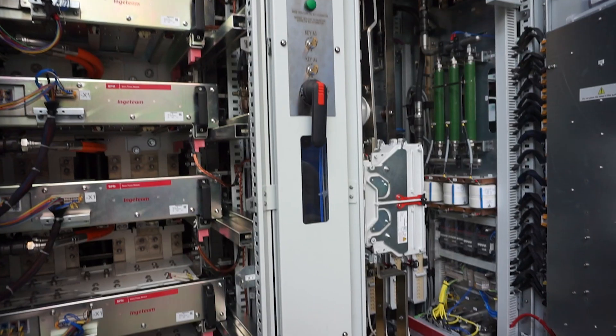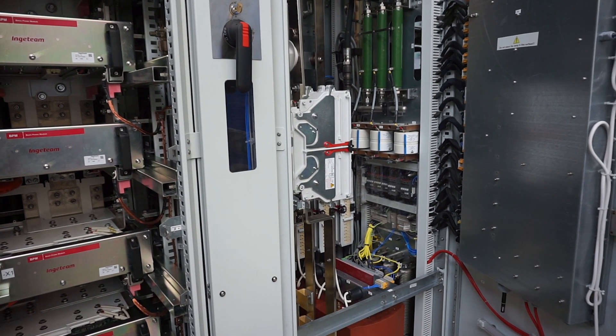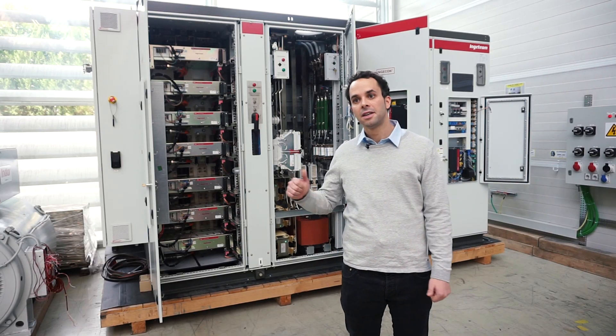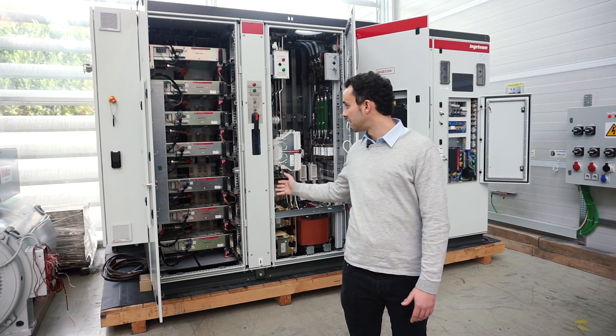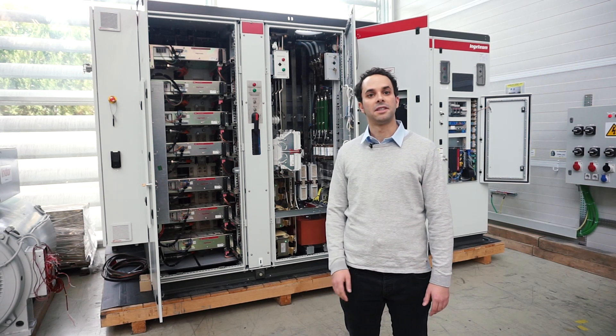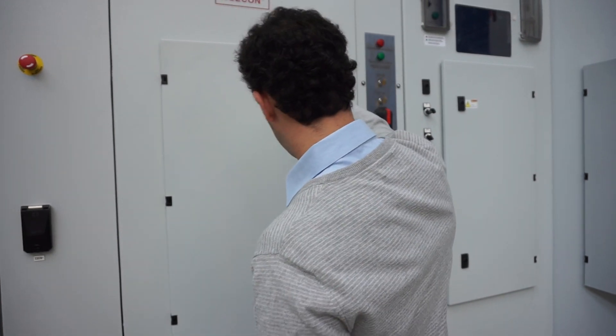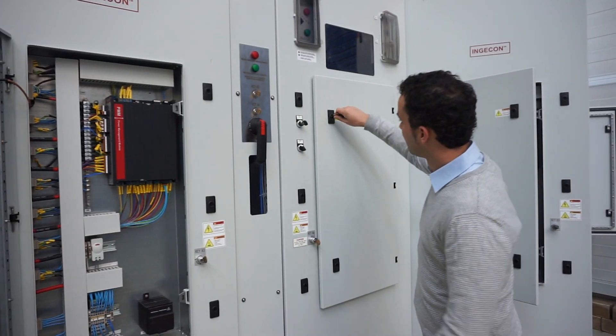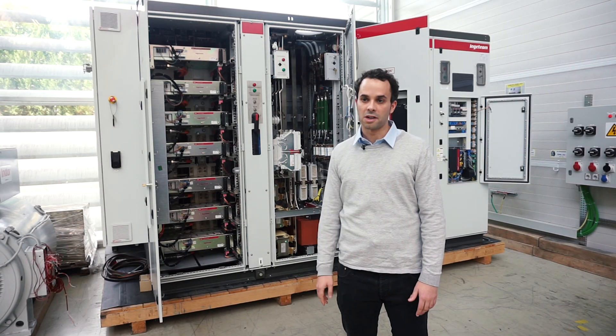We are in the last area of the lab, where we test the whole power converter. We started with the key component testing area, then followed with the power stack testing area, and at the end, the power converter testing area. Here we test both firmware and hardware products together, in order to see if the final product is ready to go to series production.